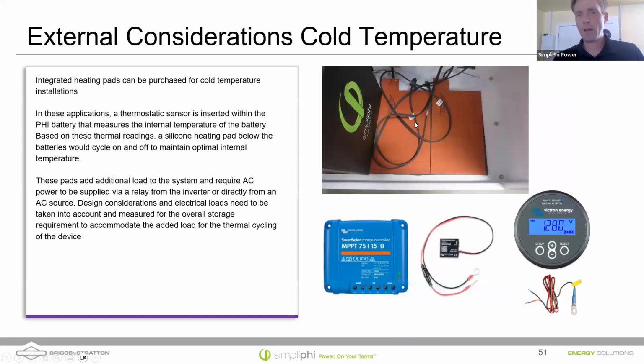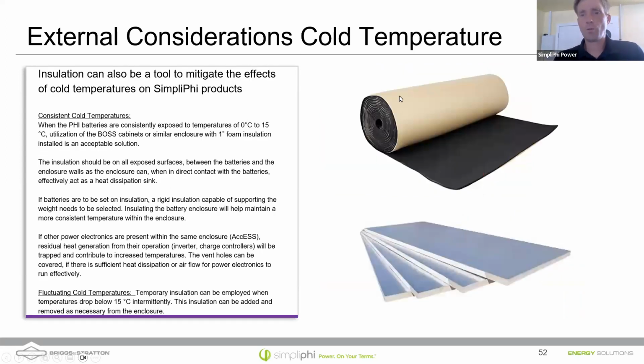One solution we have for this, we have these integrated heating pads. They can be wired directly into the BMS of the battery. If you're interested in this solution, we do have it, but it is a special order item. So if you're installing in cold environments and want heating pads to go under the battery to transfer that heat into the battery to keep them at optimal charging temperatures, these will turn on and turn off based on the internal battery temperature. So we can wire those into the batteries, give you that option. You also can use insulation in cabinets, especially in locations where you know it's going to be cold. You might throw one of these foam boards below the batteries to prevent that conduction of heat through the shelves, or use some of that foam insulation.